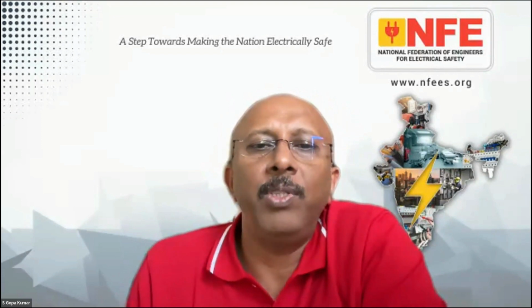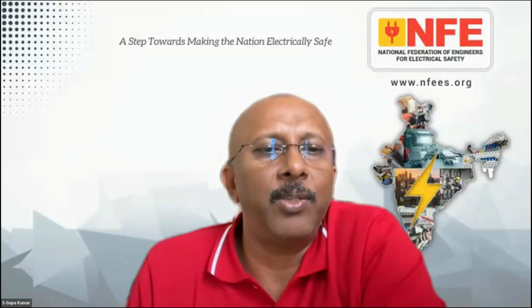There is a simple question: which is better, fuse or MCB? Probably, Krish, you can answer this. It is not a question of which is better, it is a question of the utility of the circuit. For instance, if you have a very high fault current, an MCCB will be very expensive to buy, and an MCB simply will not be able to cope with it. In that situation, the fuse is a better choice. But remember the possibility of adjustability and future changes: with a fuse you will have to change the fuse, while with an MCCB you can set a delay and do all these things. So it's not a simple fuse or MCB answer. It is a question of the utility of the circuit.